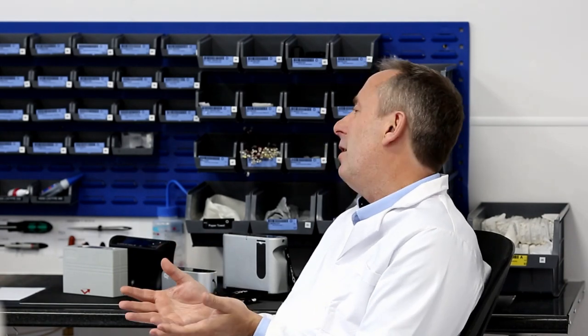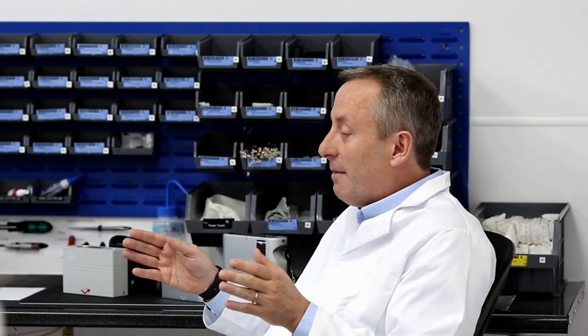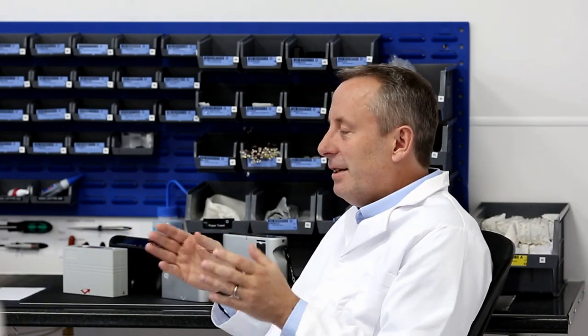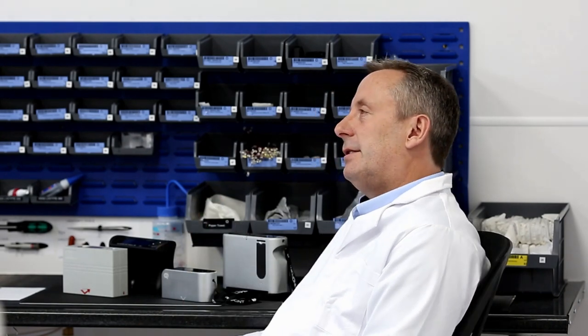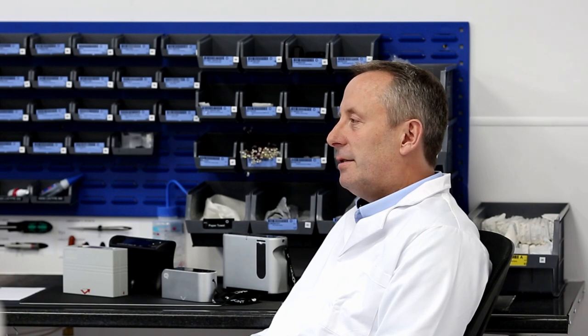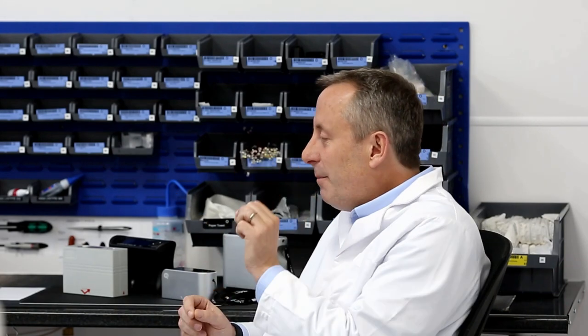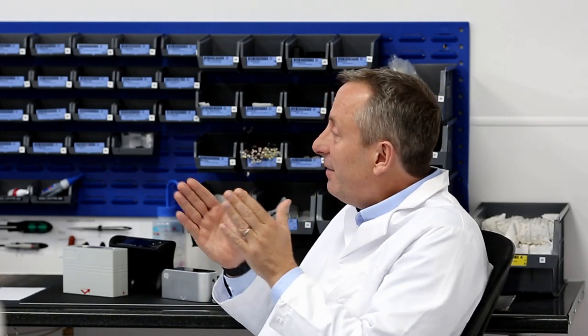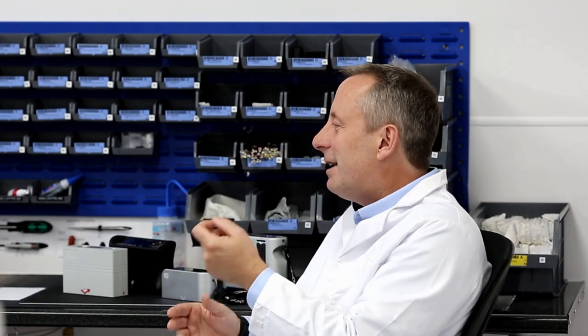That's not very good, that's a low measurement resolution. But if we're getting a good spread of the numbers and very small differences, that tallies with our eyes and that's a good measurement resolution. So for gloss, when we're measuring high gloss, if we use the 20 degree angle for anything above 70 gloss units, imperceptible differences will have a difference in the numbers, whereas if you use 60, it's much more compact and less resolution.